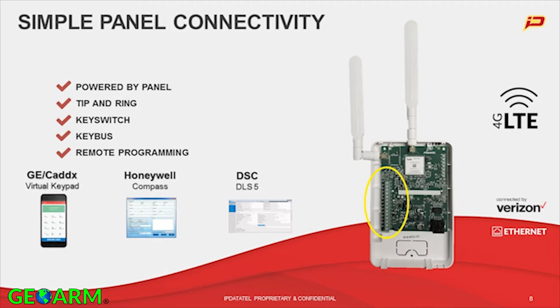For remote programming, we work with Honeywell's Compass Software and DLS5. These are free drivers available on alarmdealer.com within your portal. You can send out templates to each of your systems to make programming easier. If you don't use those programs, for these three panels especially, you can do pretty much any and all programming that you could do from the physical keypad — which makes it nice not to have to run a service call every time something goes wrong or somebody changes the user code.